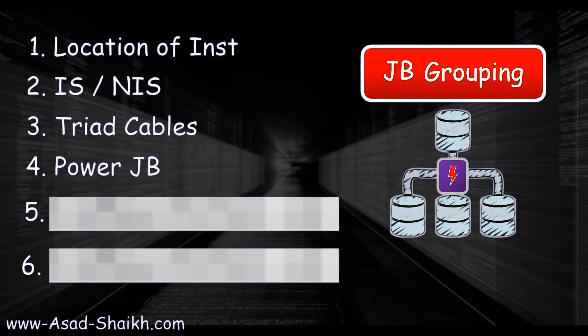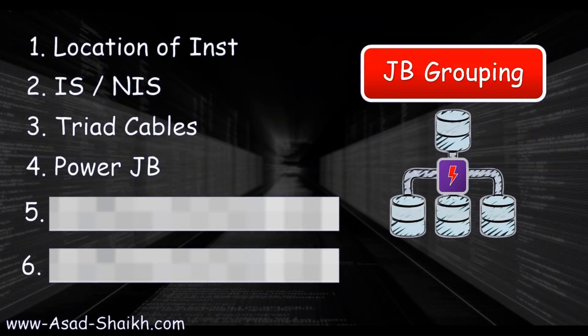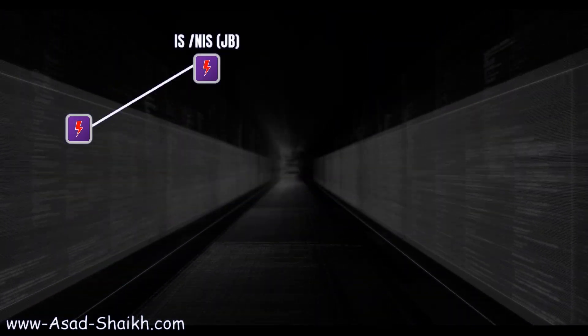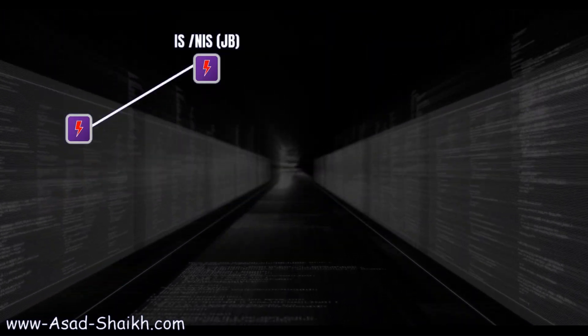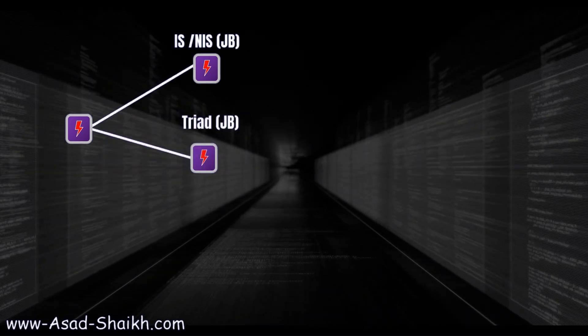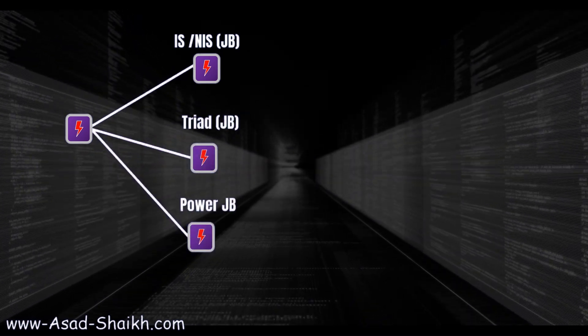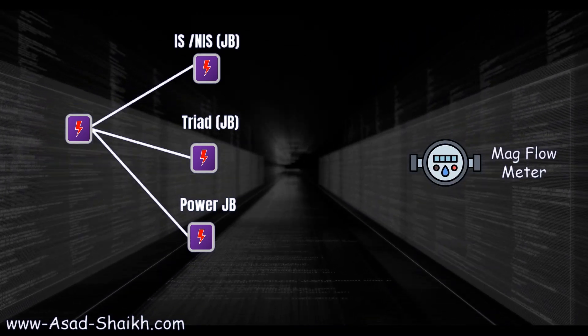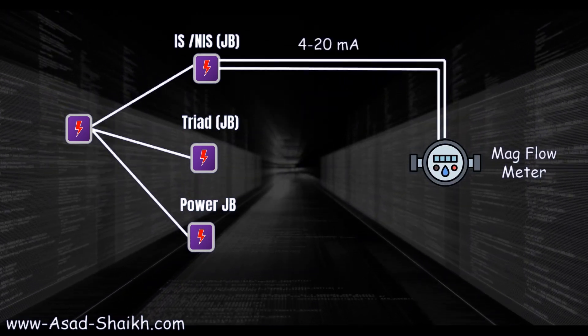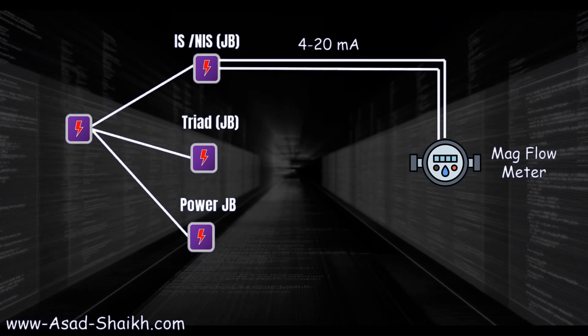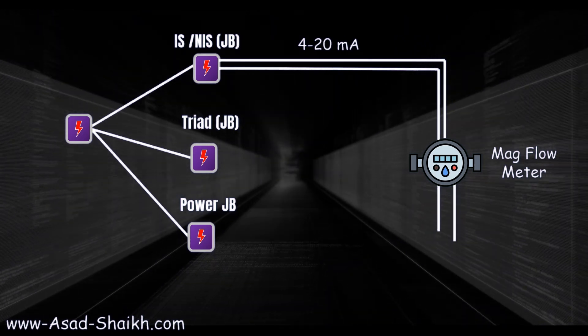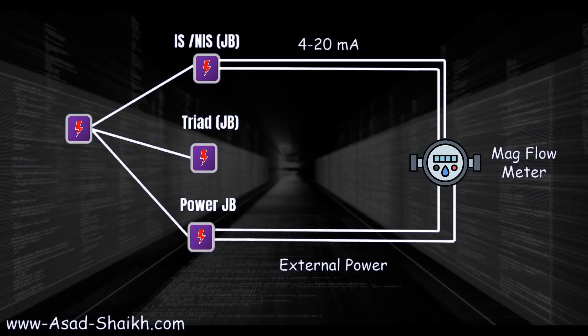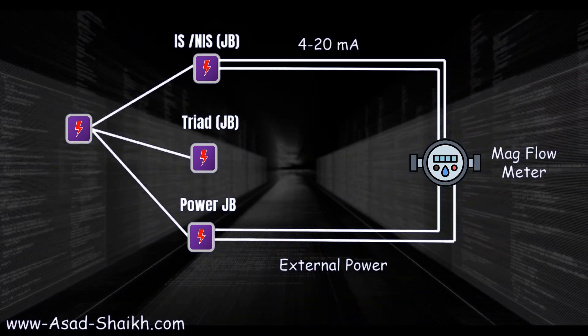The next important criterion is the power JB. Beyond IS, NIS, and triad JBs, a power JB must be kept separately. For example, a magnetic flow meter that is externally powered will have its normal 4–20 mA signal going through the regular JB, but it also needs external power — either 24V DC or AC — which comes from a separate power JB.